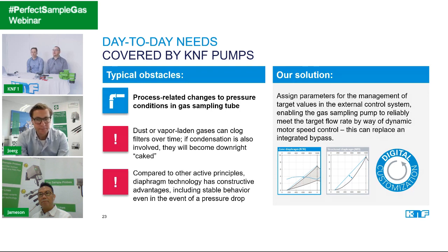But what will be the key factor in the future, I think, is the change of the digitalization. I think what we see is that we go away from the classic AC-driven motors. As you mentioned, you buy a pump, maybe you buy it big enough that these influences of pressure drops or something are not an issue. We see clearly that the future is the controllable brushless DC motor to react dynamically to these issues. If the filter clogs, the flow goes down, maybe adjust the speed of the pump to hold a stable flow. In one of your last webinars, you talked about the T90 time, for example.